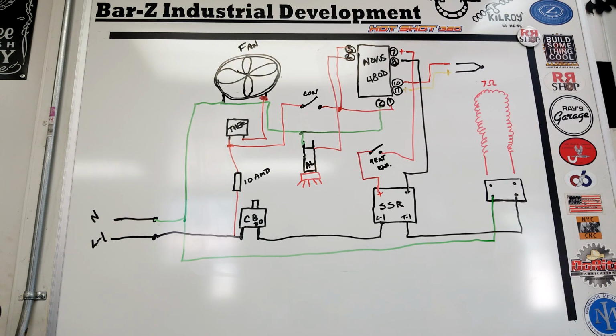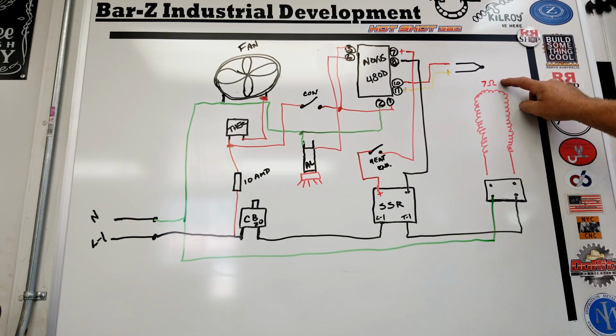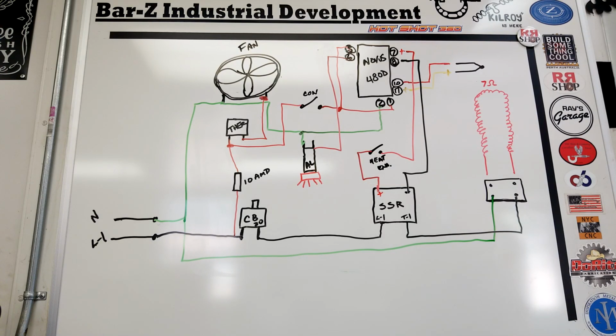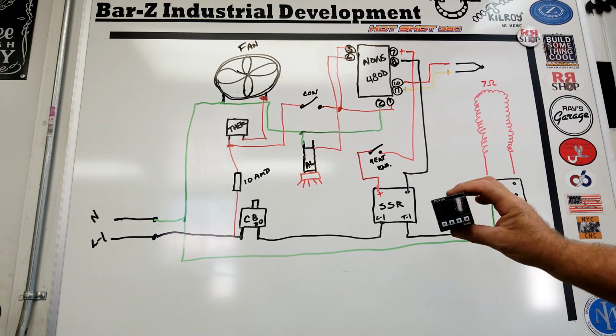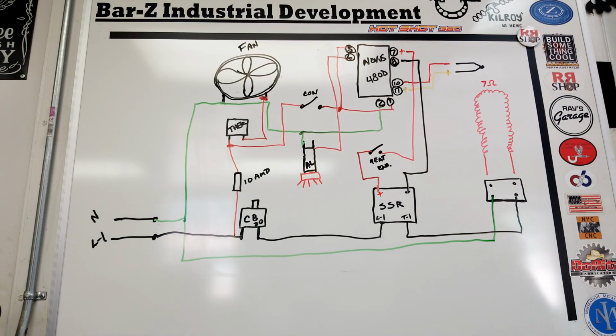Okay. We can talk about elements while we're here. This is a drawing for a 110 volt, 2000 watt unit. Your target resistance on your heating element is 7 ohms. Anywhere between 7 and 8 ohms is going to work fine. You're going to get good heating capacity there. If you're sitting about 8 ohms, you're probably at about 1800 watts right in there somewhere. Okay. But that is the wiring diagram for my standard version Hotshot. Now, if you are using some other type of controller other than a Novus, your terminal numbers are going to be different, and you need to refer to the paperwork that comes with your controller, because all this is going to change in this area. But this gives you a real good idea of how to wire your do-it-yourself ovens.